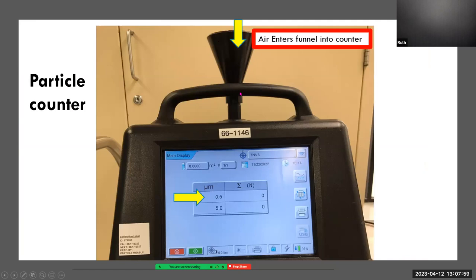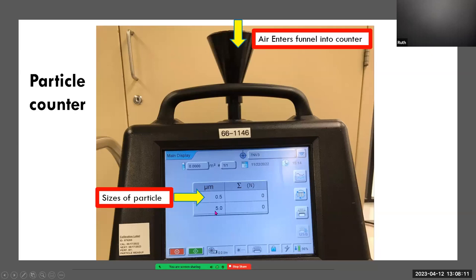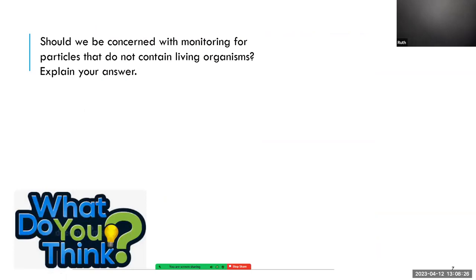For non-viable particles, we use a particle counter. Air enters the counter through a funnel and the screen monitors the size of particles in microns — 0.5 microns being very small and 5 microns being larger. The right-hand side keeps a tally of the total number of particles in the sample. So to summarize: viable means living, non-viable means not living but is a mode of transportation for living organisms.